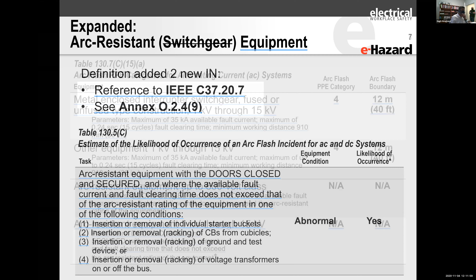And what they basically are now saying is that even if you do have arc resistant equipment, what we do sometimes on motor control centers is if we have a problem on a motor control center bucket, under certain conditions on some of the newer equipment, you can actually remove that entire bucket and replace it with a new bucket. And what 70E is now saying is that although this equipment is considered arc resistant, there is a greater risk of an incident occurring. And that is why they say, irrespective of the equipment condition now, there is a likelihood of occurrence.